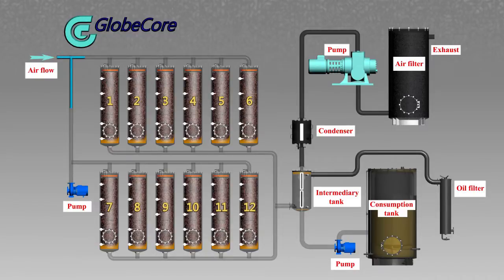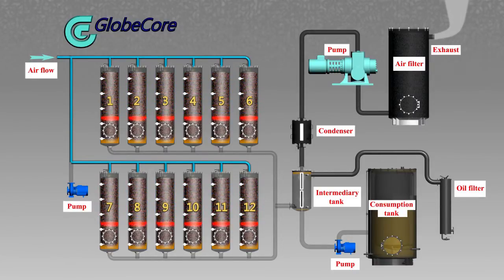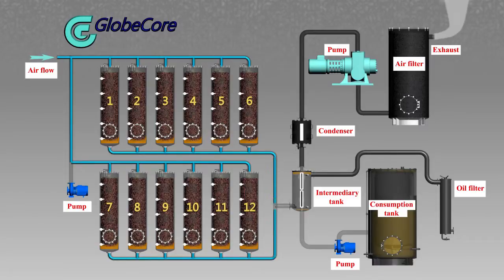When reactivation process starts, the heating system switches off. The vacuum pump creates the air flow for sorbent reactivation. All oil decomposition products are burned and are expelled from the machine after catalytic breakdown into safe, non-hazardous compounds. Reactivation lasts until the sorbent cools down entirely, which is indicated by cold air in the exhaust system.